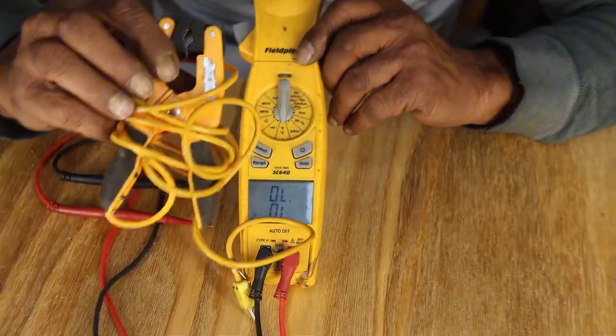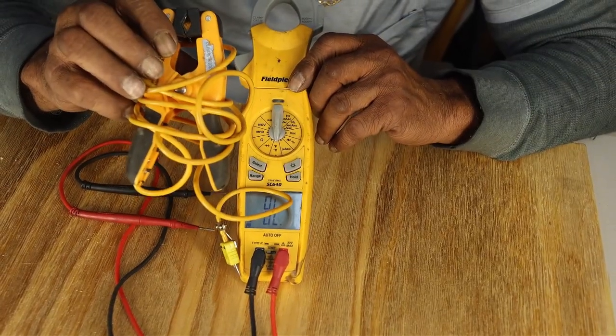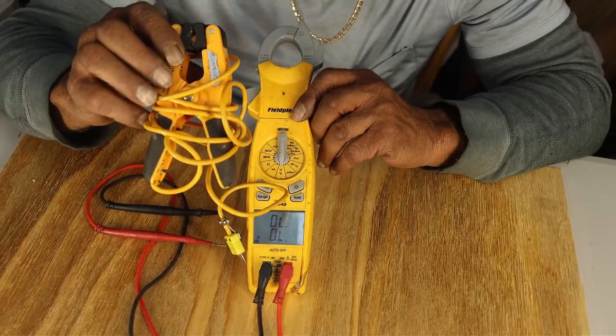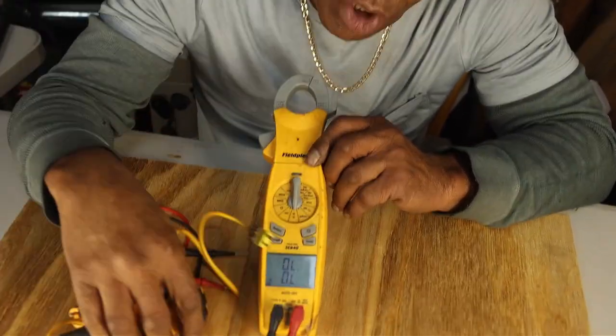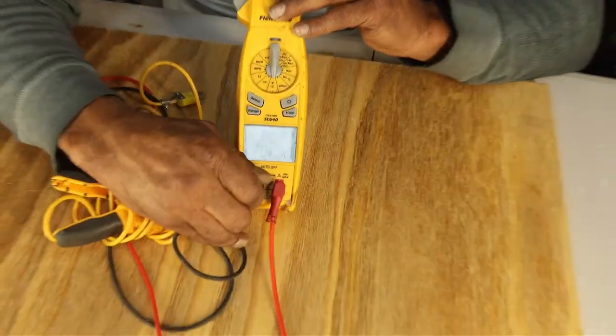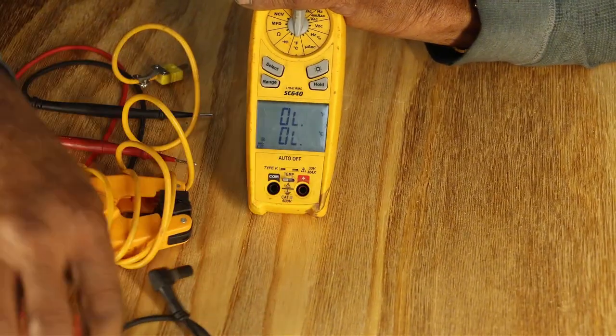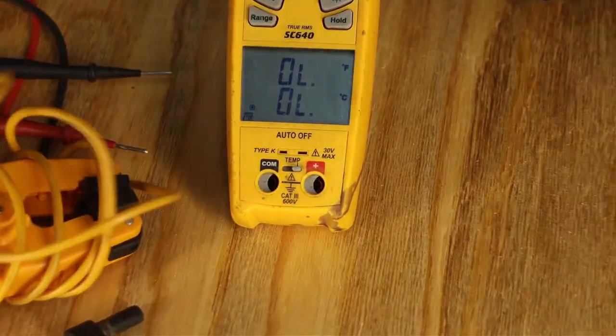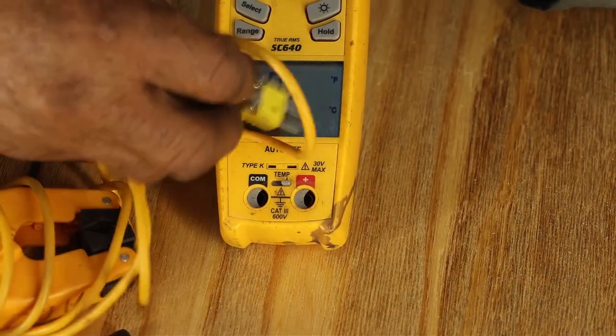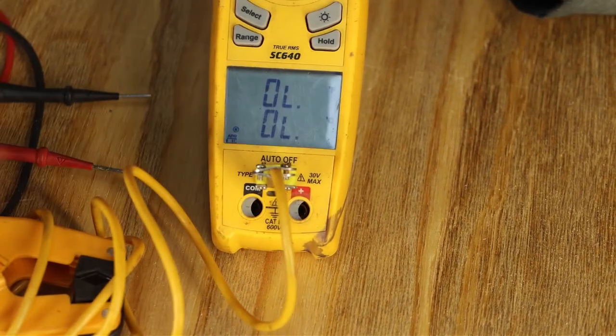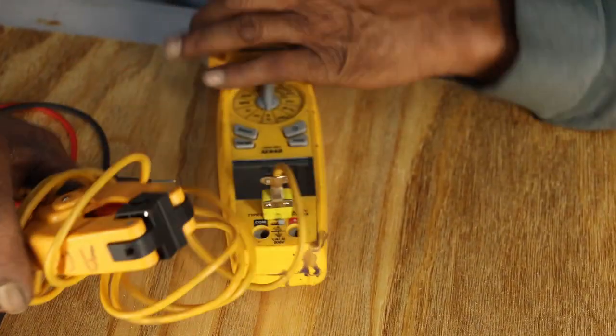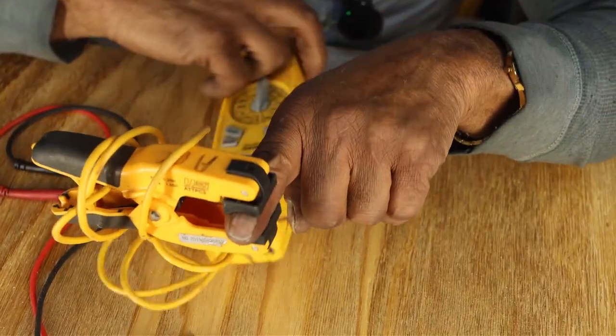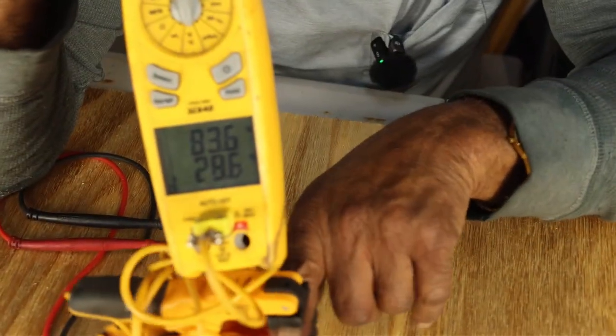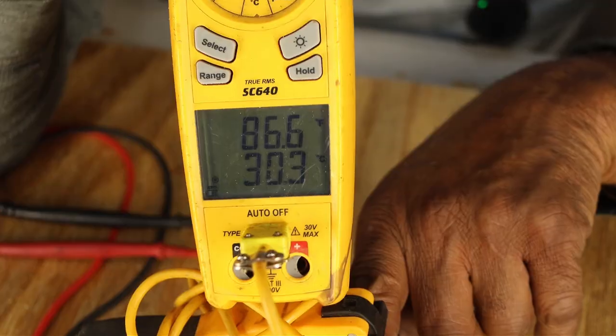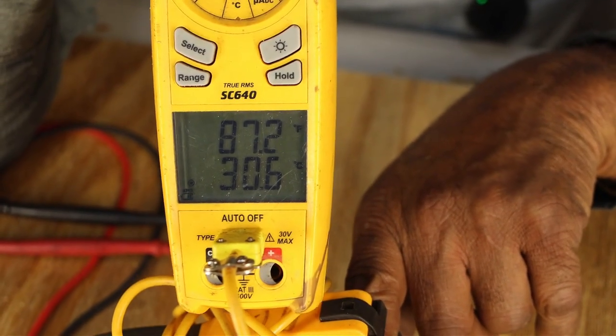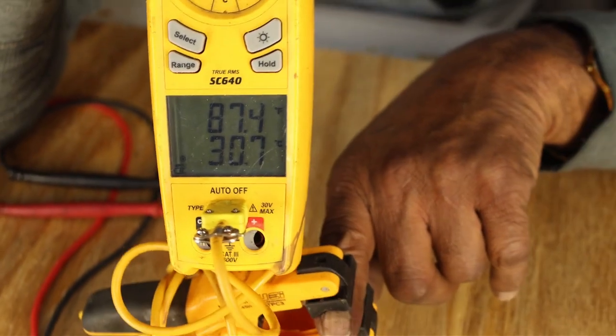Sometimes, in order to do subcooling or superheat dealing with my Freon, I need this device. If I disconnect my leads, switch this to temperature, at that point I can plug this device in, and now I can clamp that onto my copper. And when I clamp it onto my copper, my Fieldpiece will show me the temperature of the Freon in that copper. Right now, it should be showing you the temperature of my blood running through this finger.